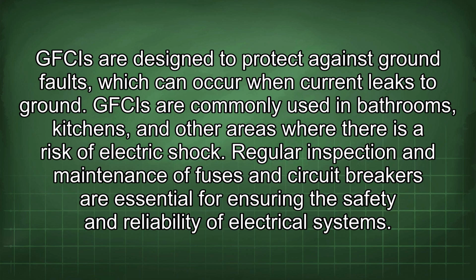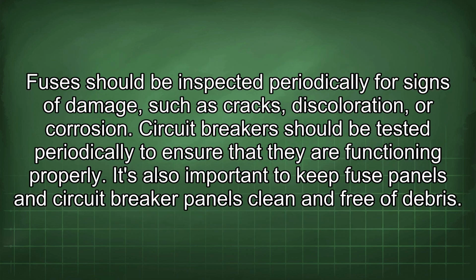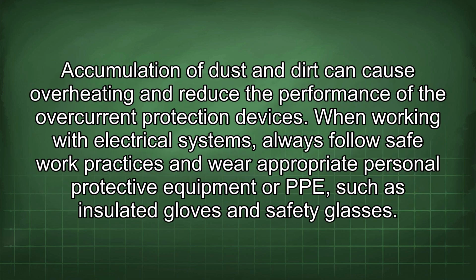Regular inspection and maintenance of fuses and circuit breakers are essential for ensuring the safety and reliability of electrical systems. Fuses should be inspected periodically for signs of damage, such as cracks, discoloration, or corrosion. Circuit breakers should be tested periodically to ensure that they are functioning properly. It's also important to keep fuse panels and circuit breaker panels clean and free of debris. Accumulation of dust and dirt can cause overheating and reduce the performance of the overcurrent protection devices.